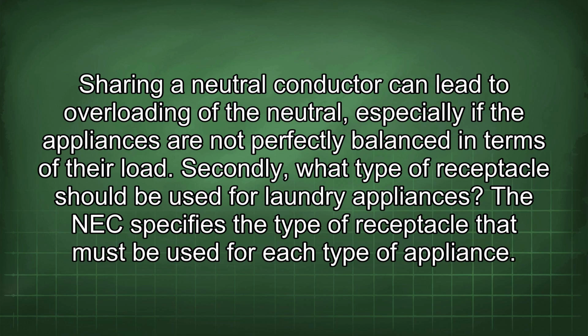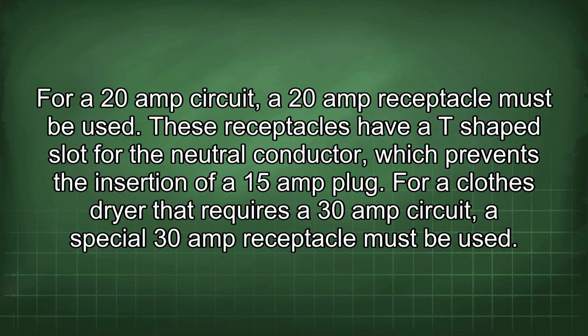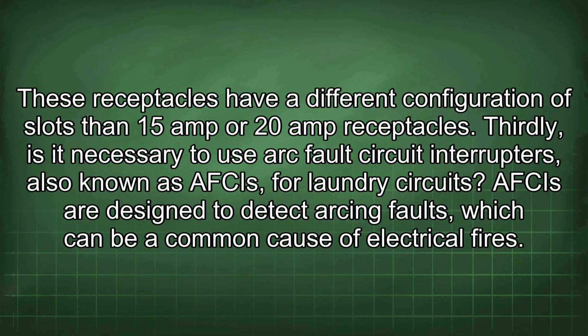The NEC specifies the type of receptacle that must be used for each type of appliance. For a 20-amp circuit, a 20-amp receptacle must be used. These receptacles have a T-shaped slot for the neutral conductor, which prevents the insertion of a 15-amp plug. For a clothes dryer that requires a 30-amp circuit, a special 30-amp receptacle must be used. These receptacles have a different configuration of slots than 15-amp or 20-amp receptacles.